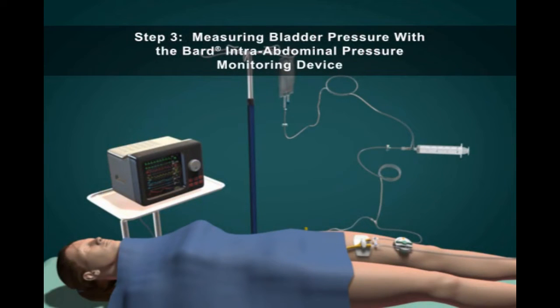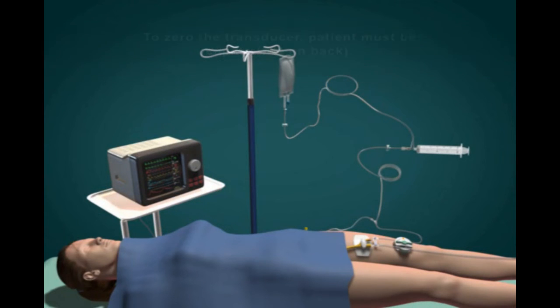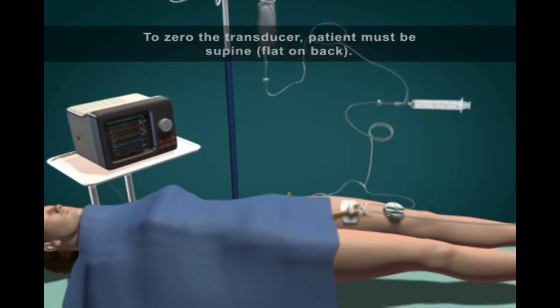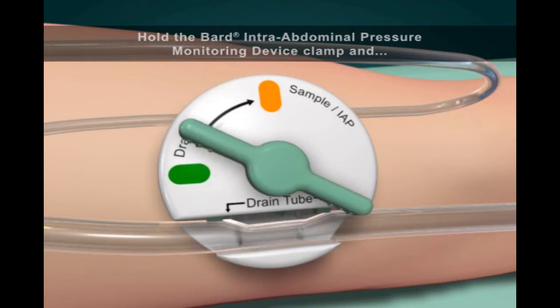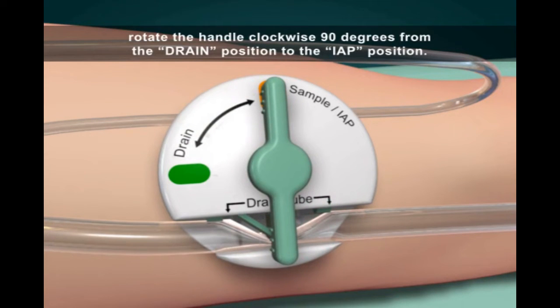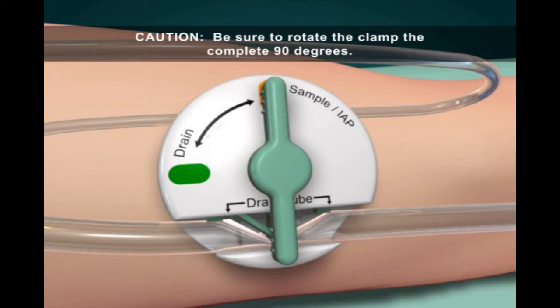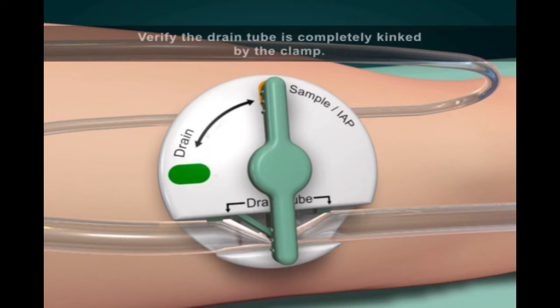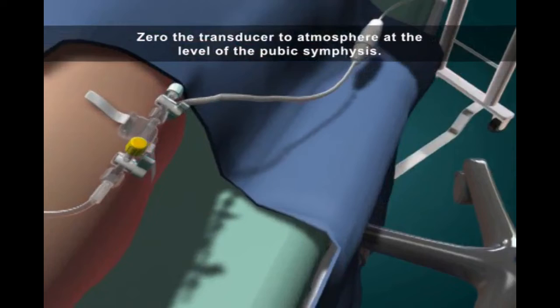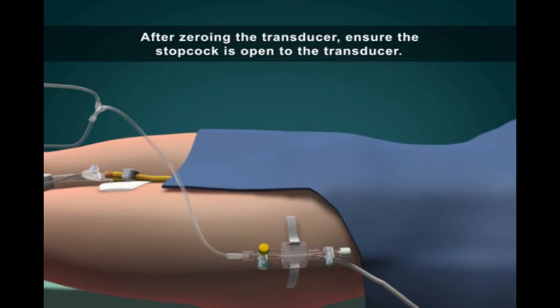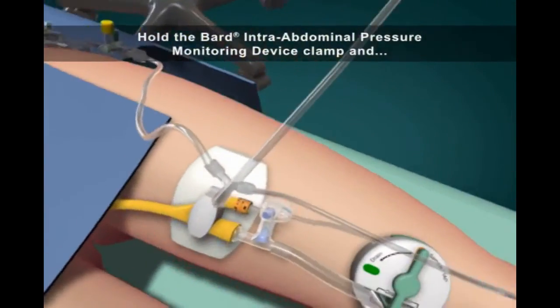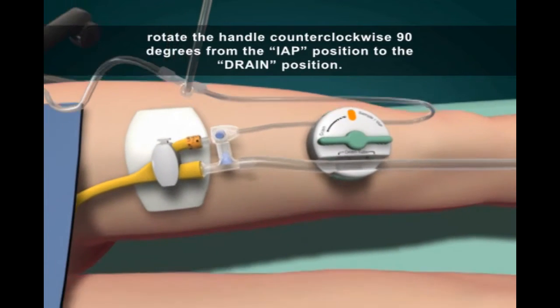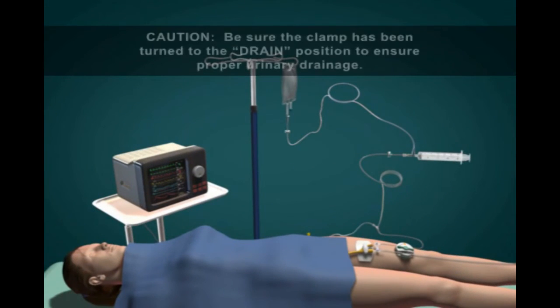Step 3. Measuring bladder pressure with the intra-abdominal pressure monitoring device. To zero the transducer, the patient must be supine. Hold the device clamp and rotate the handle clockwise 90 degrees from the drain position to the IAP position. Caution: be sure to rotate the clamp the complete 90 degrees. Verify the drain tube is completely kinked by the clamp. Zero the transducer to atmosphere at the level of the pubic symphysis. After zeroing the transducer, ensure the stopcock is open to the transducer. Hold the device clamp and rotate the handle counterclockwise 90 degrees from the IAP position to the drain position. Caution: be sure the clamp has been turned to the drain position to ensure proper urinary drainage.